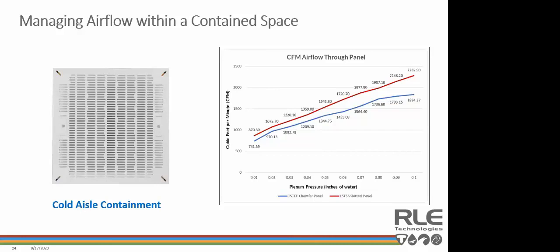Once that number is calculated, however, you can look and see how many and what type of airflow panels are needed to satisfy that IT load. As you can see on the graph, CFM through an airflow panel increases with plenum pressure. You can use a chart like this to determine which panel and how many to use for a given row in your data center. More CFM at a server rack means more kilowatts of IT load that can be cooled.